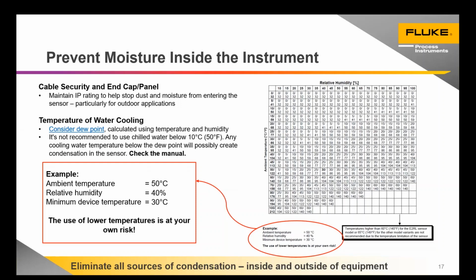I've seen a line scanner on a steel line in Slovenia a few years ago where the scanner was removed, and when you take the window off, you could actually pour water out of it. It was that bad.